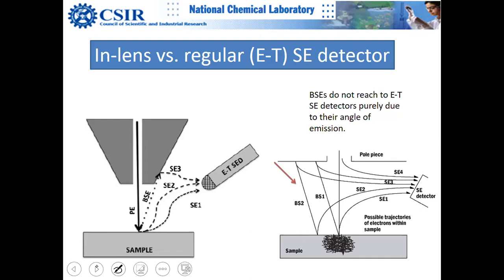This is where the invention of in-lens versus regular ET (Everhart-Thornley) detector design becomes important. The secondary electron detector can attract all kinds of SE1, SE2, and SE3 because it is positively charged. These take zigzag paths and all get pulled to the detector.